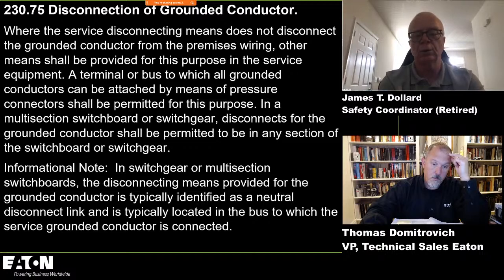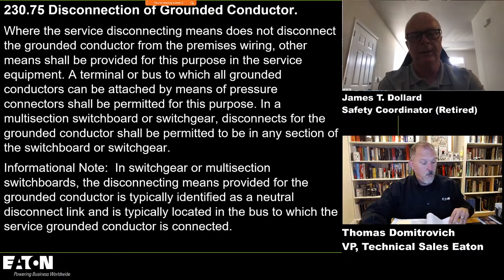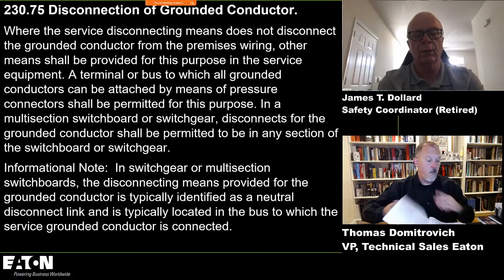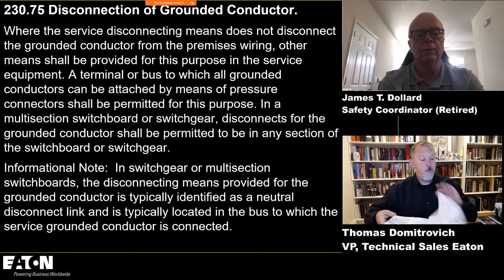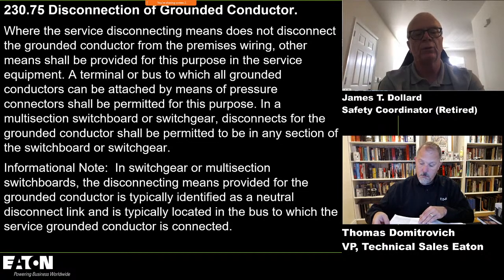They were in an older building replacing some lighting, and they shut the circuit off they were working on. He was an apprentice. He didn't fully understand multi-wire branch circuits, and he got hung up on the neutral. One of the reasons for this requirement is so that we can remove that neutral link when we're doing GFCI testing. Ah, good point. Yeah, that's right. You've got to remove that to do that testing.